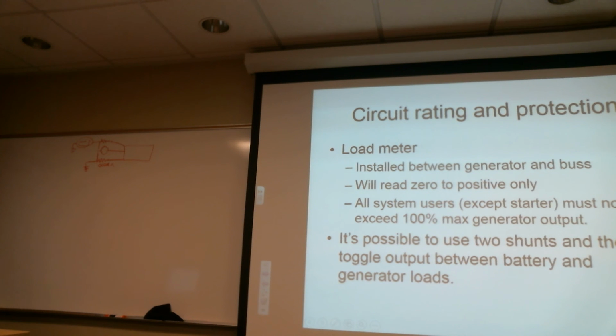So if something else is going wrong, I'll know immediately that I've deviated from normal output. Whereas with the discharge and charge of the battery, that'll be gradual - it'll take 10 or 15 minutes. Remember, if the generator stopped working, the battery is above its normal voltage, its surface charge, so it'll take a while for that to start coming down. Then I realize, wait a minute, battery's declining, something's wrong.